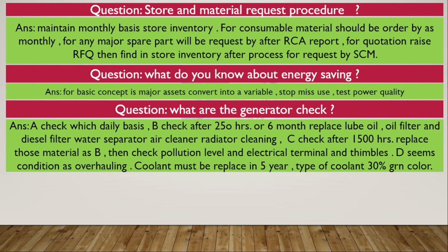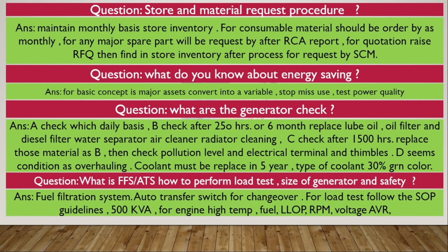Question: what are the generator checks? A check is on a daily basis. B check is after 250 hours or 6 months: replace the lube oil filter, diesel filter, water separator, air cleaner, and clean the radiator. C check is after 1500 hours: replace the same materials as in B, then check the pollution level, electrical terminals and thimbles. D check is overhauling, and the coolant must be replaced in 5 years. Type of coolant: 30% green color.